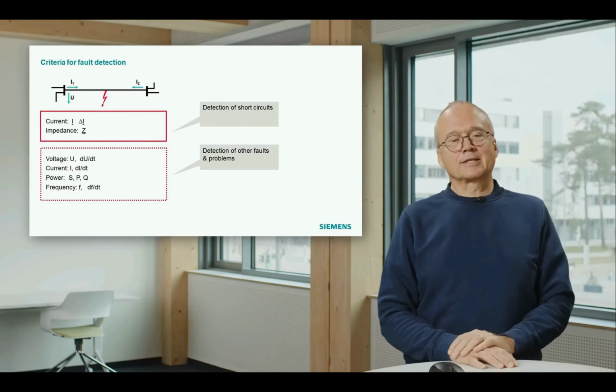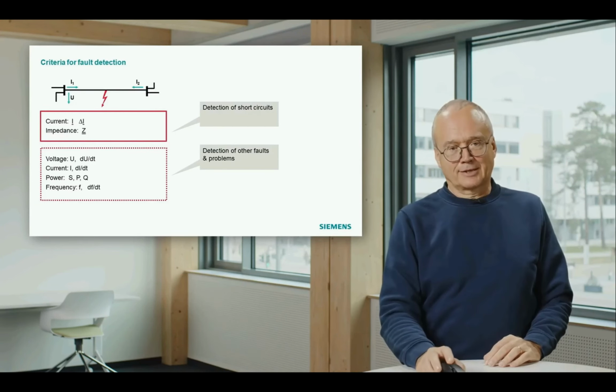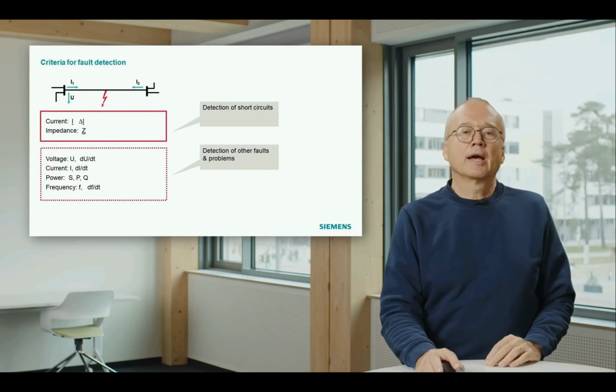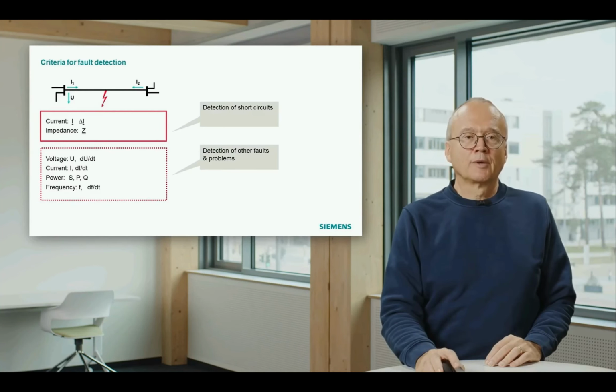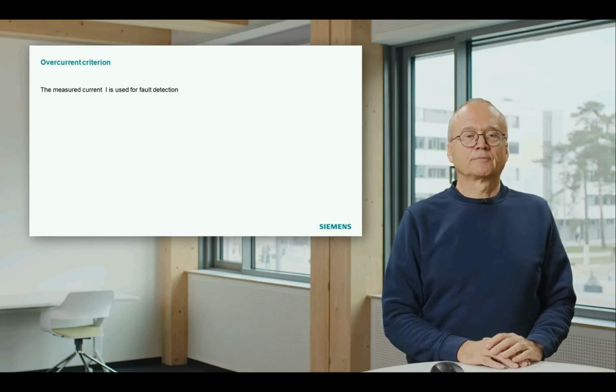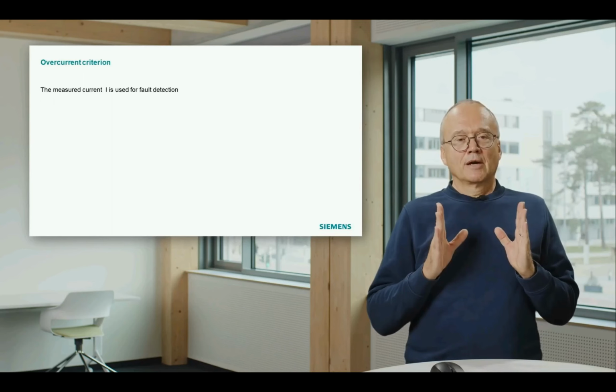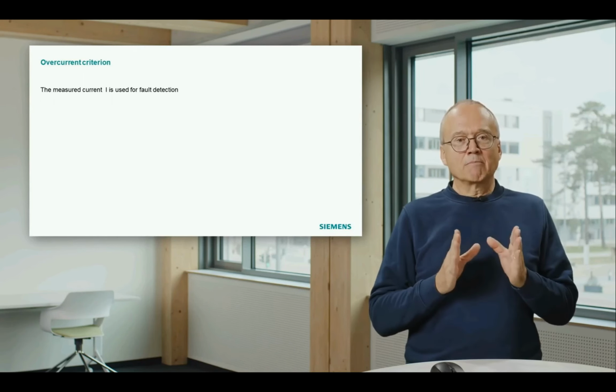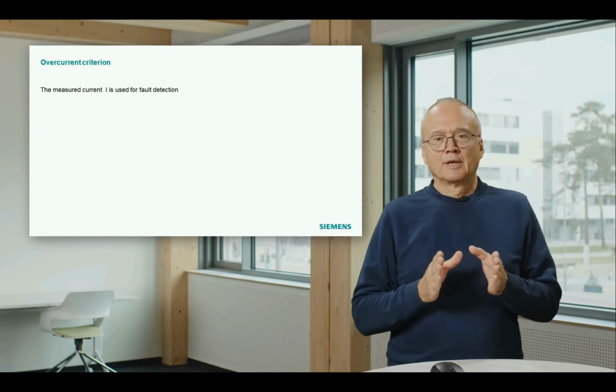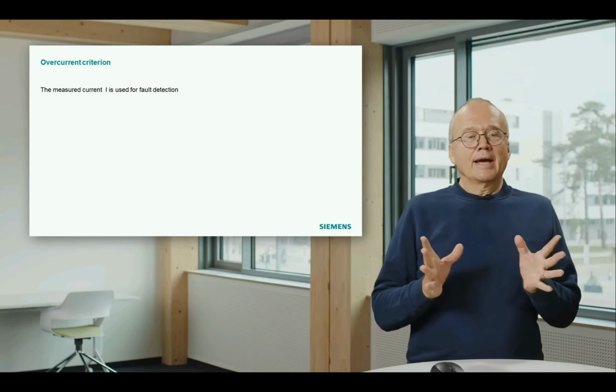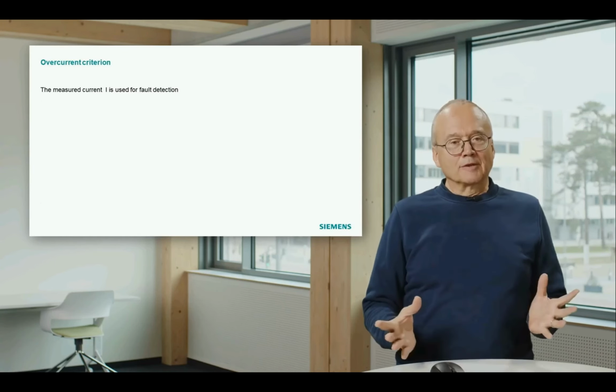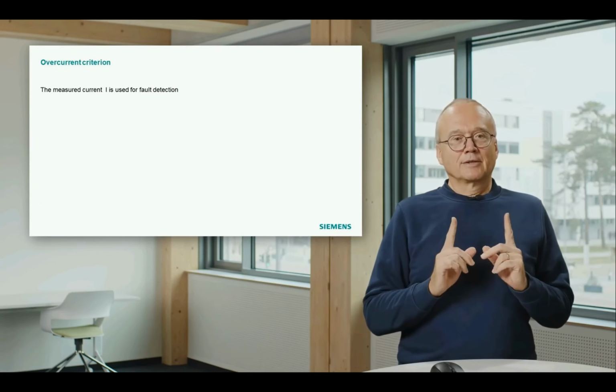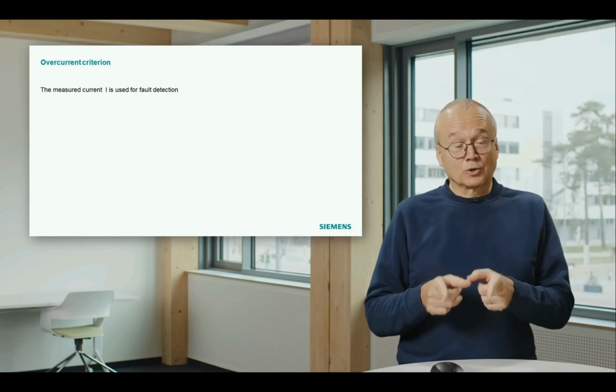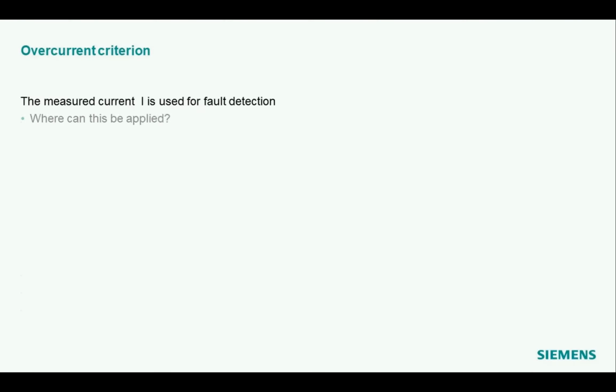We will now, in the next slides, focus on the detection of short circuits, and we will start with overcurrent protection. That means our device only measures the current, and the job of the device is now to detect: is there a fault, a short circuit on the line or not? How can this be done?